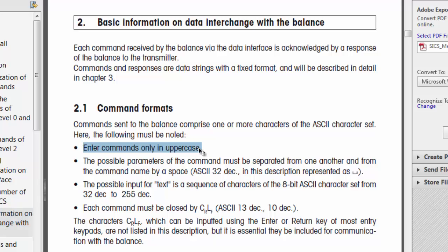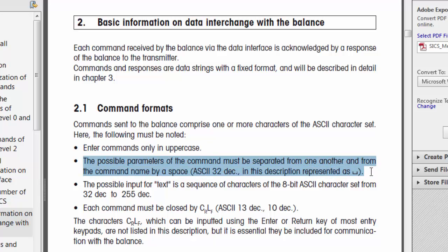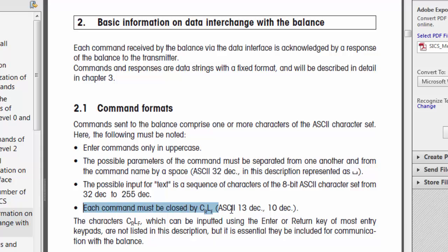First, as you can see here, commands should only be entered in uppercase by the communications master. Commands are separated by spaces, and the documentation uses a special character — an underscore-type character — to denote where a space should be included. Additionally, each command must be closed by a carriage return and a line feed at the end, and the carriage return and line feed will also be returned by the device at the end of each response.